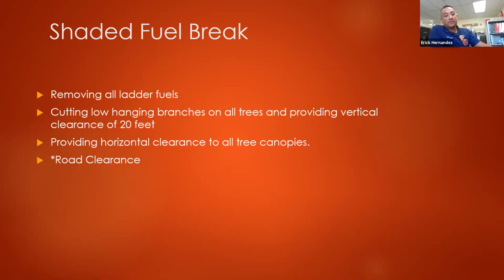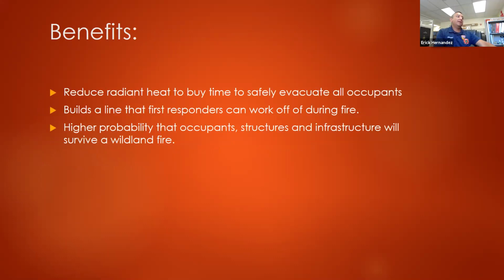And then the road clearance, that's another big one. Road clearance, always look at your means of egress. You should be making sure that in an emergency, not only can you get out of the property and then to the public right of way, but also we can come onto the property. And the benefits, again, you reduce the radiant heat to buy time to safely evacuate all occupants, and it builds a line that first responders can work off of during a fire.